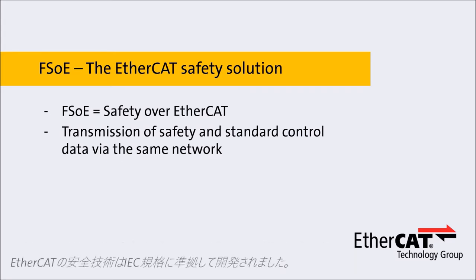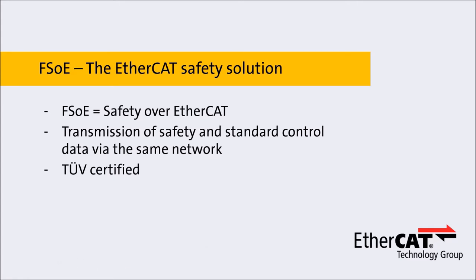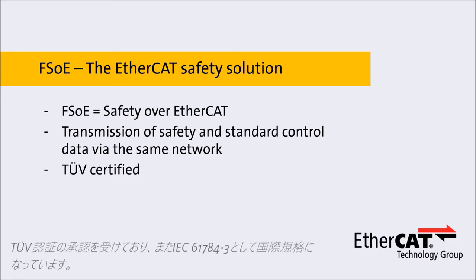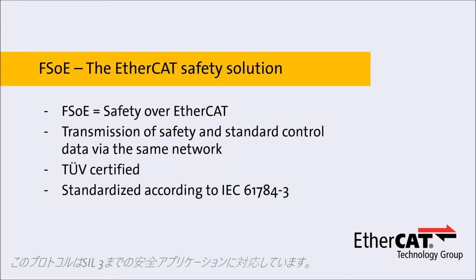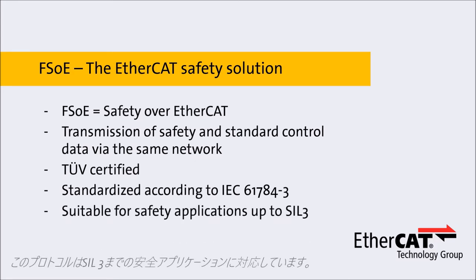The EtherCAT safety technology was developed according to an IEC standard. It is TÜV certified and standardized according to IEC 61784-3. The protocol is suitable for safety applications up to Safety Integrity Level 3.